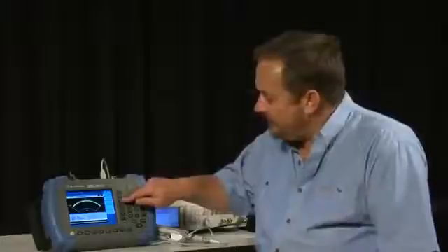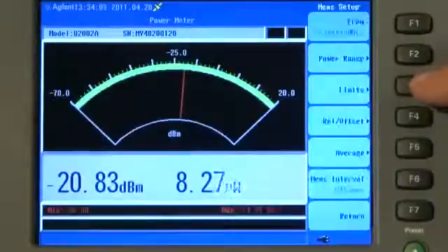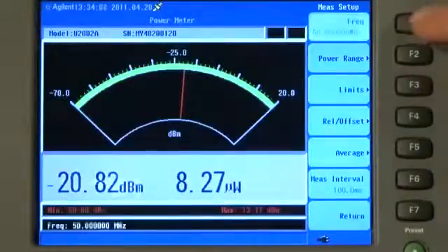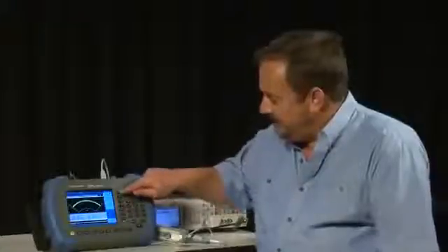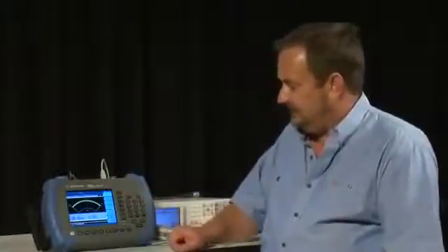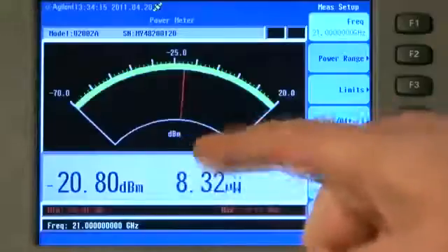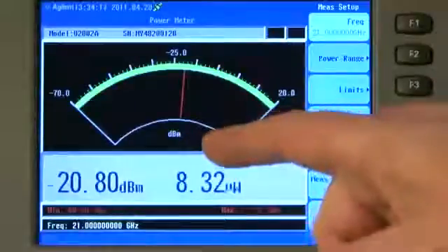Now don't forget, before we start making an accurate measurement, we do need to tell the analyzer what frequency the signal is that we're measuring so that it can load the correct calibration constant. So I'll just press Measure Setup and select Frequency and I'll enter 21GHz. And now we're making an accurate calibrated power meter measurement of our 21GHz signal.